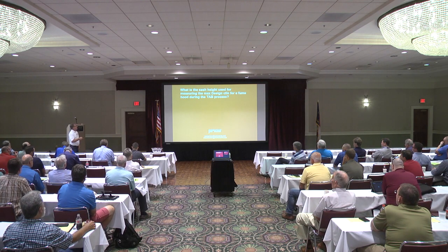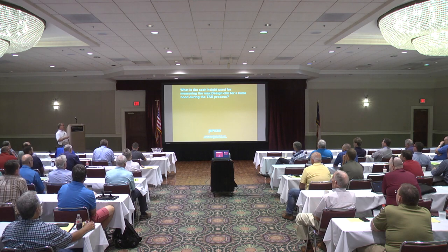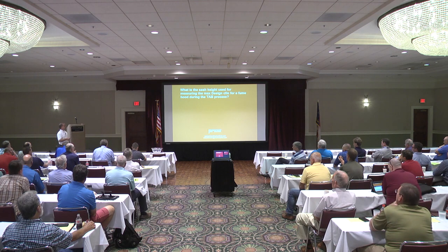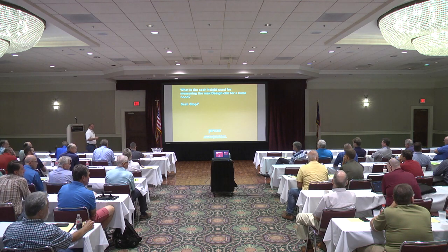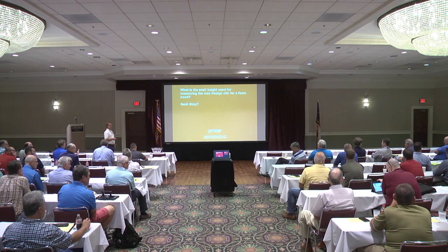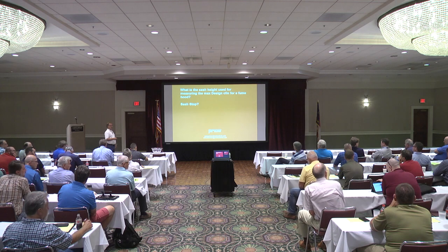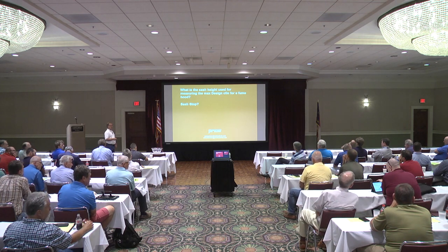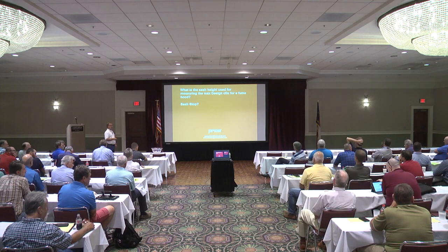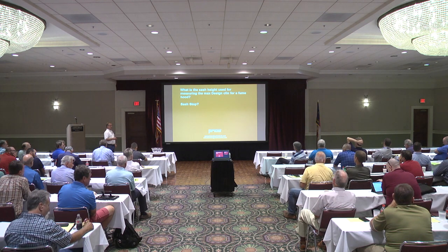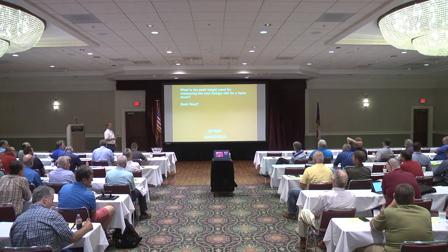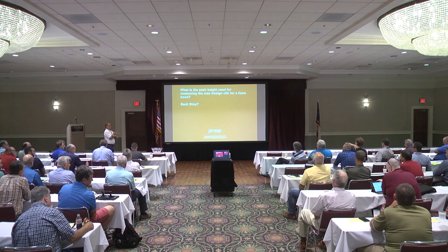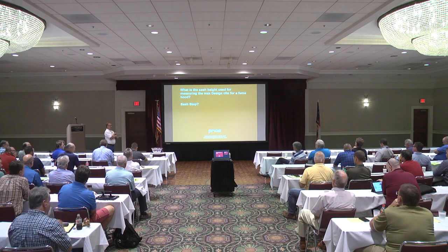So, back to the same question. What is the sash height used for measuring the max design CFM for a fume hood during the test and balance process? Sash stop? Yes, sir. Well, I just finished doing two different science buildings. They have two different types of hoods, and each one is different. We have 12 inches, 14 inches, 18 inches. And that was the working height of the hood. That's what they were going to use them at. So that's how we measured it.